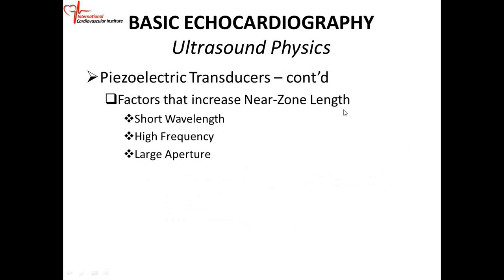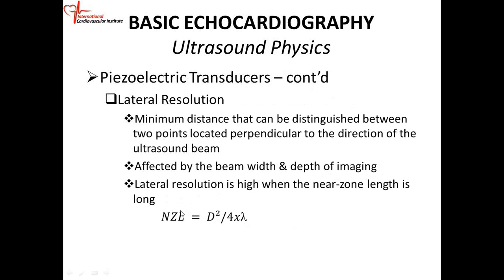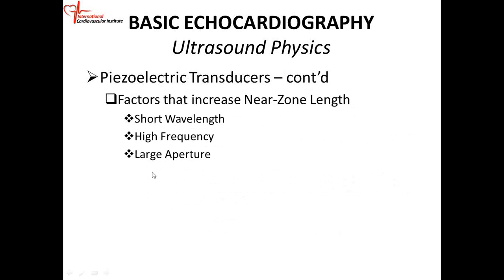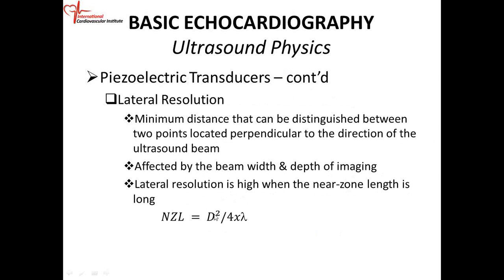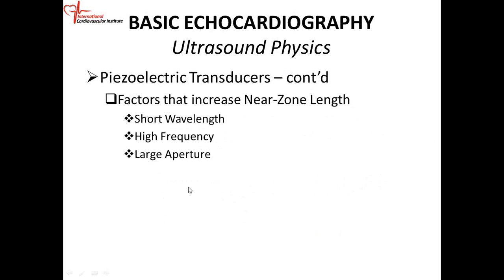All right, so these are the factors that affect the near zone length. The factor that increases the near zone length is a short wavelength. So the longer this number is, the greater it is if the wavelength is short, or if your aperture, which is the diameter, is large. That's the diameter of your transducer. That's what they call the aperture. If the diameter of the transducer is large, it's going to increase your near zone length and hence the lateral resolution. If the wavelength is short, then it's going to increase your near zone length and increase the lateral resolution as well.